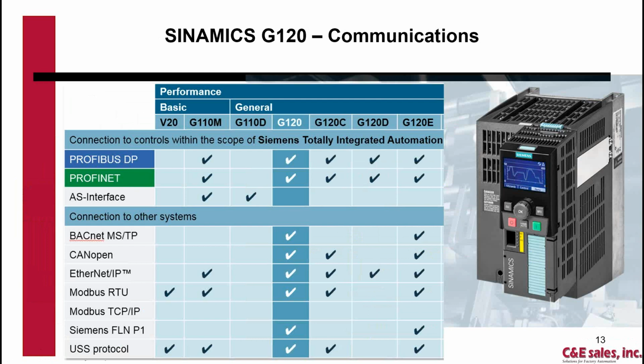So this slide really highlights some of the network differences and capabilities of the drives. You see the V20 there at the left. The V20 only has the capability of Modbus or USS protocol. On the G120C, we see a lot of the industrial protocols: Profibus DP, Profinet, CANopen, Ethernet IP, Modbus RTU, or USS. Then the G120 also, with that CU230, can do the building automation protocols, BACnet and Siemens FLN.